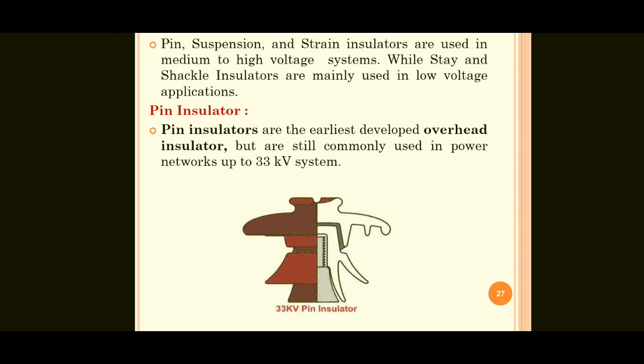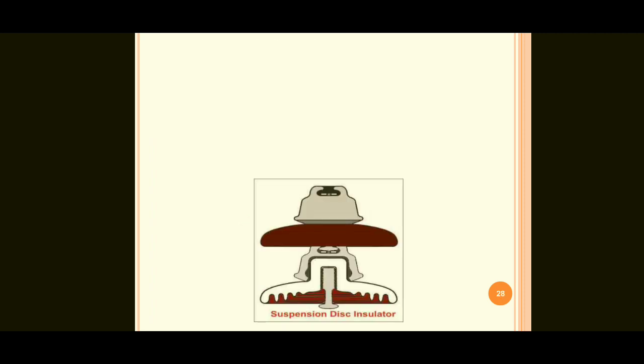First one, pin insulators. Here this figure shows the pin insulator. Pin insulators are the earliest developed overhead insulator, but are still commonly used in power networks up to 33 kV system. So where a 33 kilovolt system is there, use the pin insulator. The voltage range is limited up to 33. In general, what is the range? 11, 33, 400, like that. The ratings are present. So up to 33 kilovolt use the pin insulator.